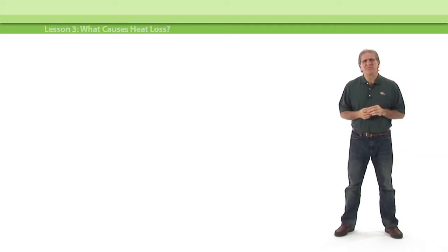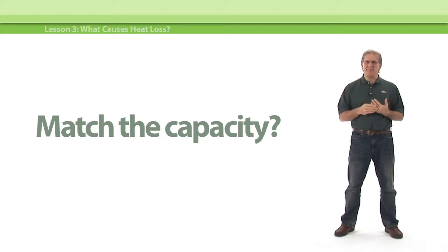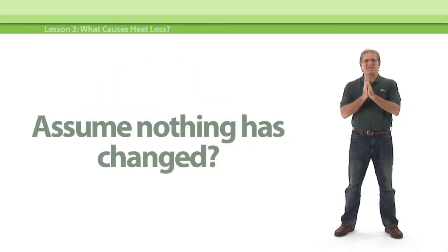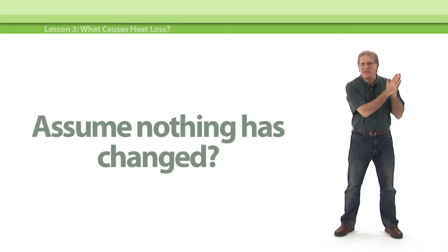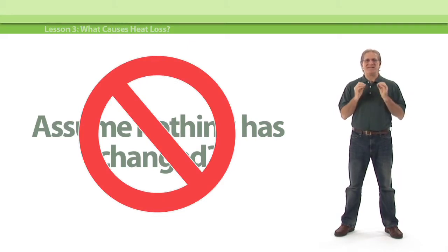So, how did you size the replacement boiler on your last few jobs? What did you write down? Now, if you just match the capacity of the original boiler, or if you say that you measure the baseboard to get the installed heating load, you're making some assumptions that aren't serving you or your customer very well. First of all, you're assuming that the guy who put that boiler in 30 or 40 years ago knew what the heck he was doing. And second, you're also assuming that nothing has changed in the structure over the last 30 or 40 years since that boiler went in. A lot has changed in boilers since then.